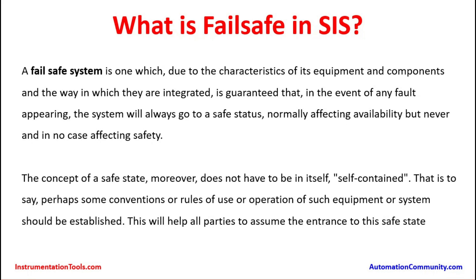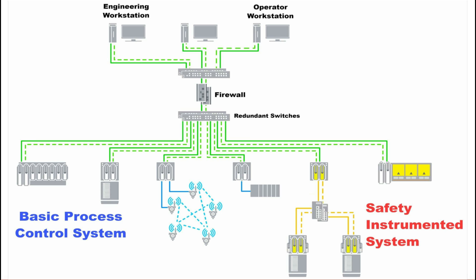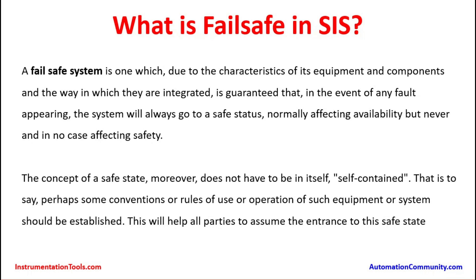The safety system is a passive system — it is kept ready and not acting, unlike a control system. In a control system, sensors are sensing and the DCS controller is giving action to the control valve, which is always moving — perhaps 0.5%, 1%, 2%, or 5% depending on the requirement. Whereas safety instrumented system valves do not perform control; they take preventive action during hazardous conditions. The systems are ready to act but in a passive mode.